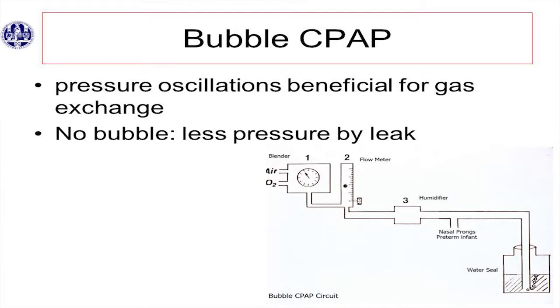Bubble CPAP. They tell us that the advantage of bubble CPAP is that because of the bubbling, you get oscillations, and these pressure oscillations are beneficial for gas exchange. So you need to have the bubble. If you have bubbling, you have the CPAP pressure reached. If you have leak and there's no bubbling, you also don't reach the CPAP pressure. So is it true that the pressure oscillations are beneficial for gas exchange?